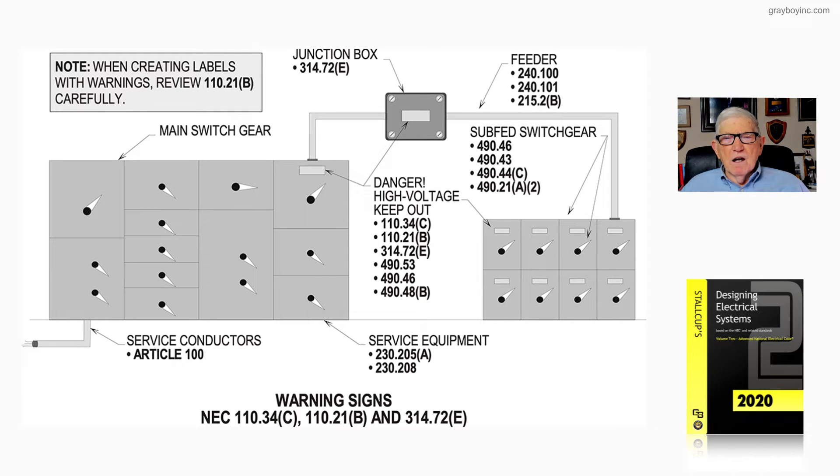Notice that 110.34C is really the main section for switchgear, switchboards, panelboards, and things like that. 110.21B covers field markings and labeling of equipment. 314.72E, as seen above in the junction box, requires a label. 490.53, 490.46, and 490.48 provide labeling requirements for switchgear, switchboards, and panelboards.